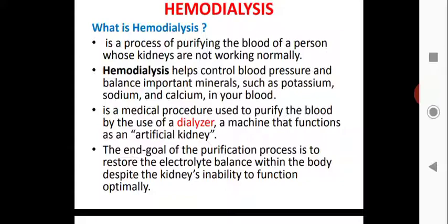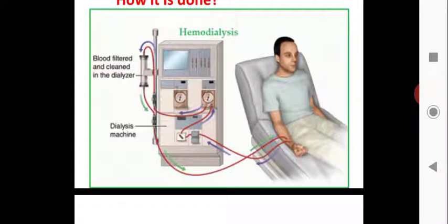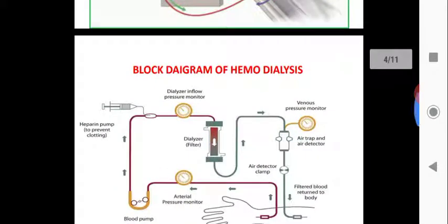You can see a pictorial representation showing one green arrow towards the patient and a blue arrow from the patient to the hemodialysis machine. The blue arrow is from your artery and the green arrow is towards the veins. Blood is taken from the artery, fed to the blood pump, then to the dialyser. After the dialyser, the purified blood is fed to the vein.